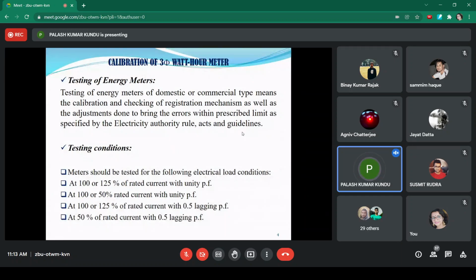So it is necessary to check the registering mechanism as well as the disc rotation that may have the error. That means the disc can rotate with a high speed or with a lower speed. So the rotation of the disc needs to be calibrated in terms of the meter constant or the error in the meter constant, as well as the rotation of the disc is mechanically linked with the registration mechanism.